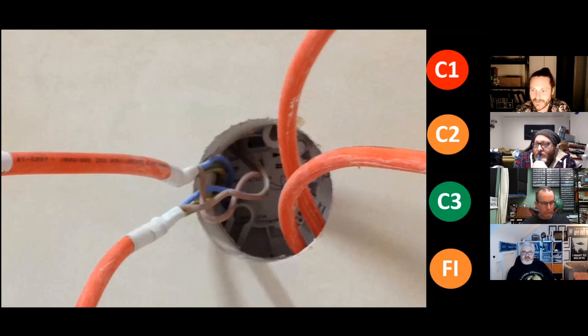But it's four FPs. As far as I'm aware, you don't bring four FPs into one base unit or one detector or sounder. It's not exactly how a loop really works, but maybe I'm wrong. Maybe this is a new spider junction configuration that we're all missing. Is that sort of from above, looking at the back of the detector or the sounder, and the other two are sort of going off somewhere else, perhaps? Yeah, it does, doesn't it? It looks like they're just disappearing. Maybe there is a surface patress there to allow some cables to loop through it on into a bit of YT, maybe.